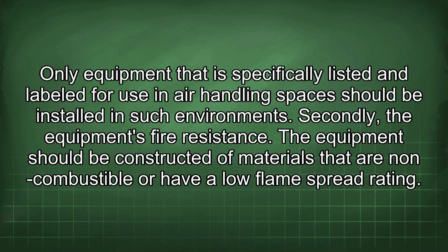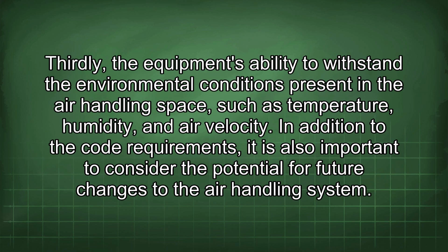Only equipment that is specifically listed and labeled for use in air handling spaces should be installed in such environments. Secondly, the equipment's fire resistance. The equipment should be constructed of materials that are non-combustible or have a low flame spread rating. Thirdly, the equipment's ability to withstand the environmental conditions present in the air handling space, such as temperature, humidity, and air velocity.